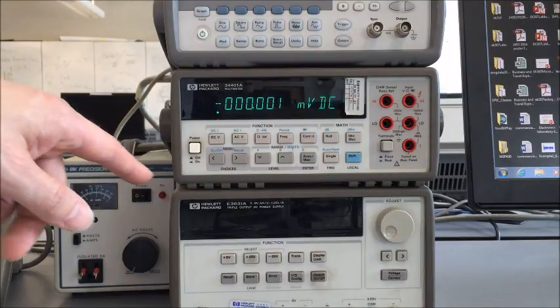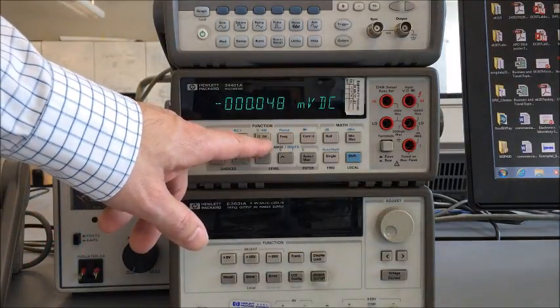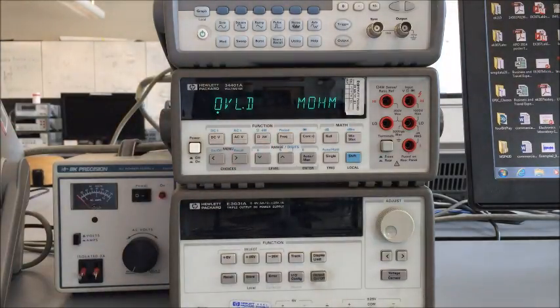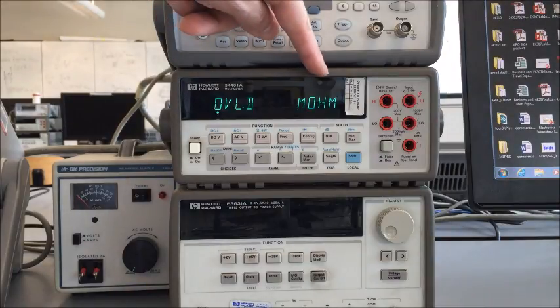If we want to measure resistance, we need to change the function. We push the ohm 2-wire button. Now we can see the display changes to measuring ohms.